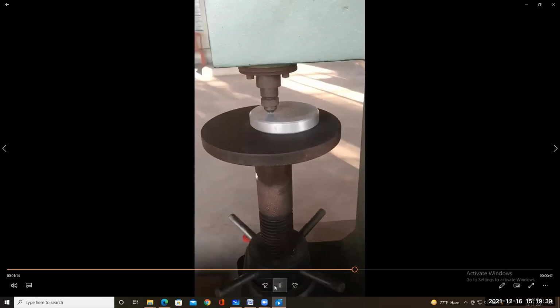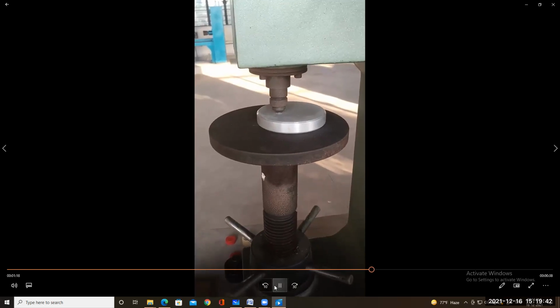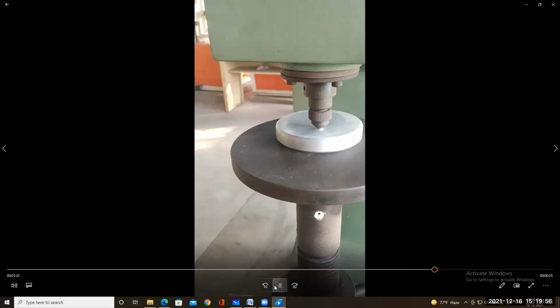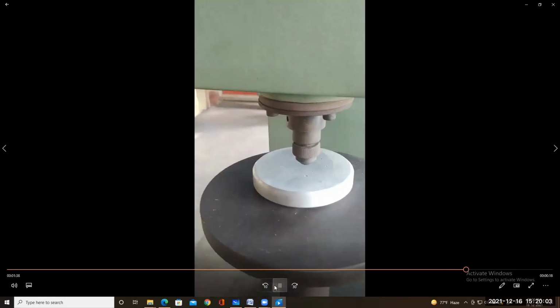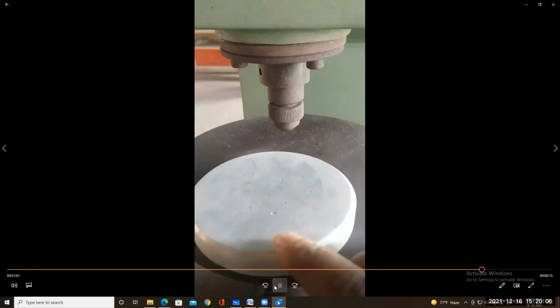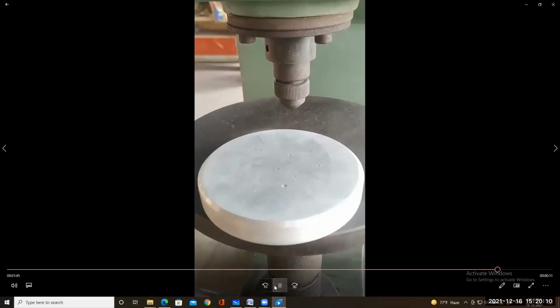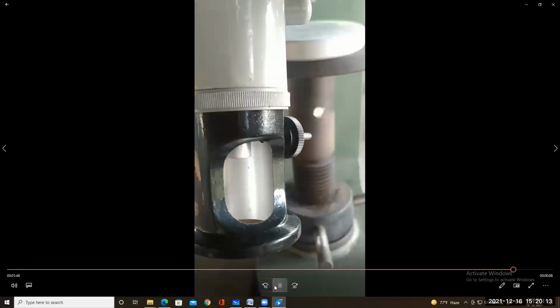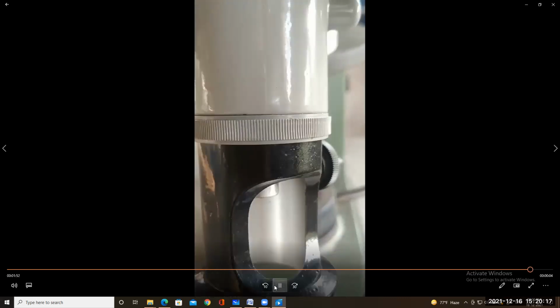Now I am creating the impression by moving the load actuating rod clockwise so that it engages the indenter to the workpiece, and keeping it as it is for more or less 5 to 10 seconds, and then unloading the indenter. The lifting device is brought downwards so that the impression created can be visible, which is here. The diameter of this impression can be measured by means of the microscope itself, with an accuracy of plus or minus 0.01 millimeter.